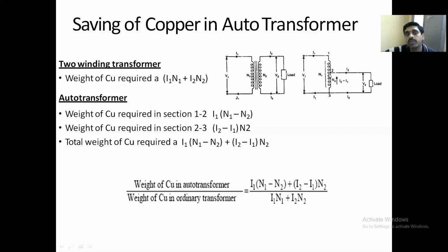If you take the auto transformer, what is the weight of the copper required in section 1, 2? In this section 1, 2 it is I1 into (N1 minus N2). In this other section, what is the copper required? (I2 minus I1) into N2. Therefore, the total weight of the copper required is the sum of these two. That means I1 into (N1 minus N2) plus (I2 minus I1) into N2.